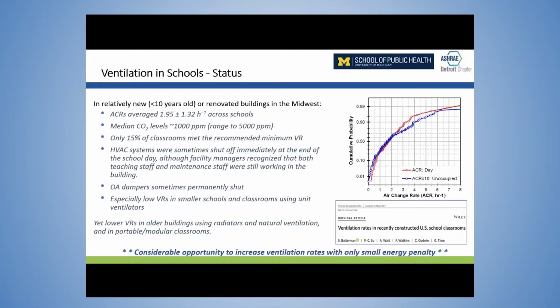And we often find problems in portables and modular classrooms. The only thing unique probably in Michigan, I would say, is that we have a lot of older schools and we have both a significant heating and cooling cycle. So we're using a lot of mechanical systems typically, for heating and cooling quite frequently. There's considerable opportunity to increase ventilation rates with only small energy penalties.